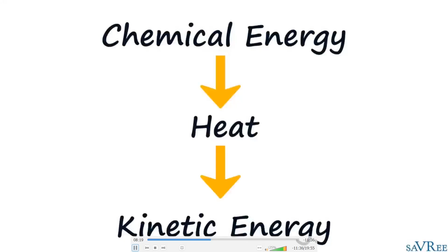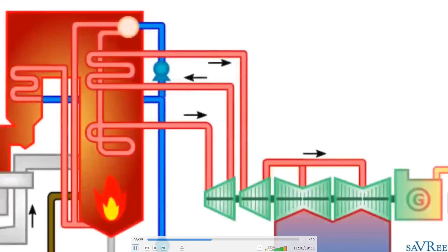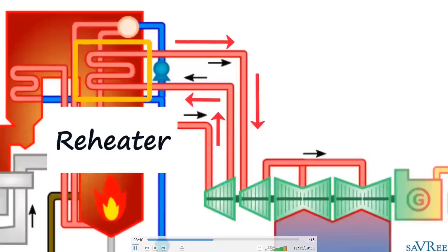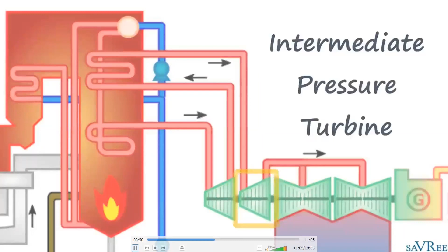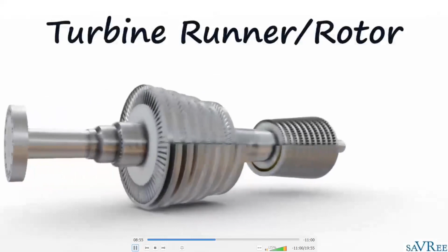We're then going to take the steam out of the high pressure turbine. It's given up a bit of its heat already, but we send it back into the boiler to be reheated so that we can send it then to an intermediate turbine. The reason we reheat the steam is simply because we get a slight increase in efficiency, so it's definitely worth doing. We feed that steam from the reheater in the water tube boiler to an intermediate pressure turbine. The process is the same as for the HP turbine, the high pressure turbine.